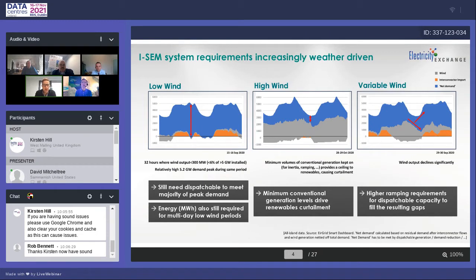In the middle chart, this is a particularly high wind period. The biggest challenge here is overnight, where you've got high wind on the system and low demand, and keeping enough conventional generation on the system to provide the necessary system reliability and inertia. At the moment, that's providing a ceiling on the amount of renewables we can accommodate on the grid and leading to curtailment.